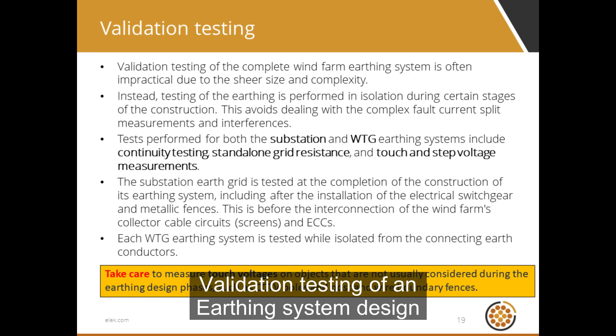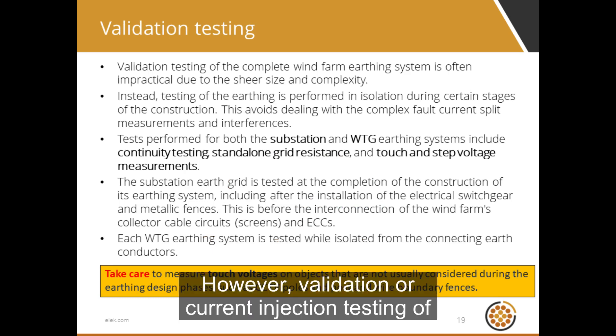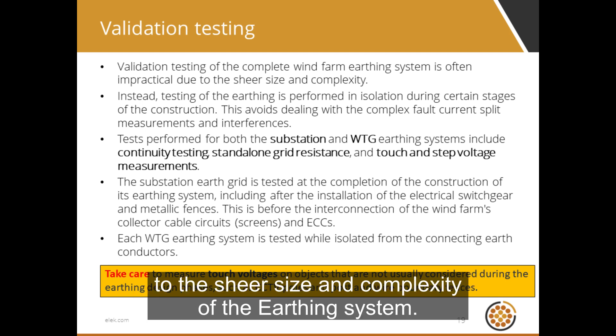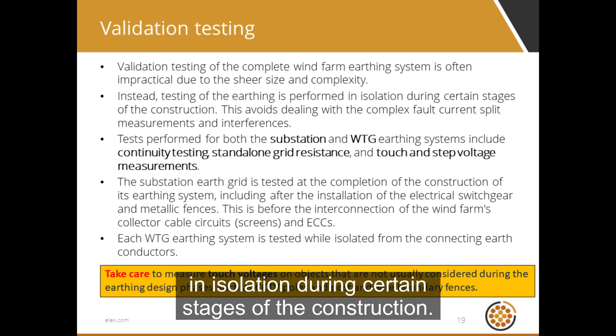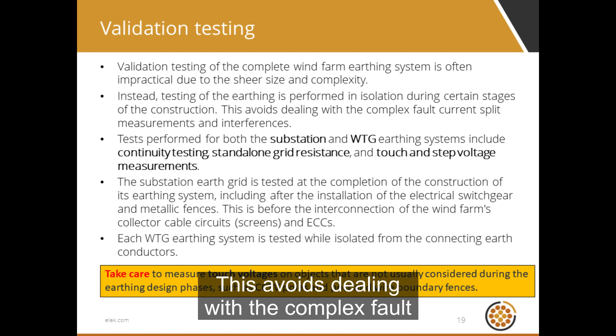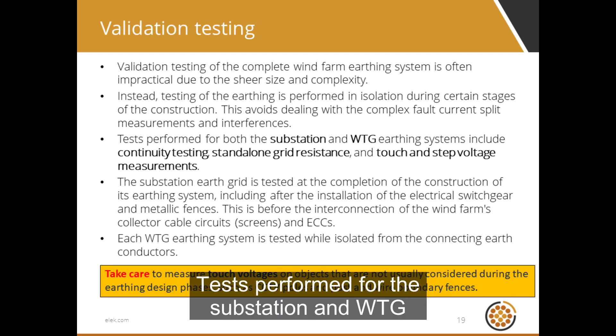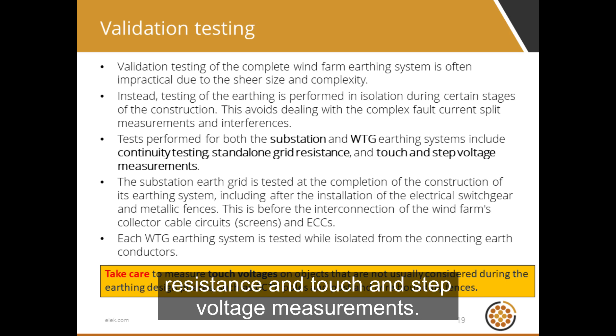Validation testing of an earthing system design is an important final step. However, validation or current injection testing of the interconnected wind farm earthing system is often impractical due to the sheer size and complexity of the earthing system. Testing of the earthing is performed in isolation during certain stages of construction, avoiding complex fault current split measurements and interferences. Tests performed for the substation and WTG earthing systems include continuity testing, standalone grid resistance, and touch-and-step voltage measurements.